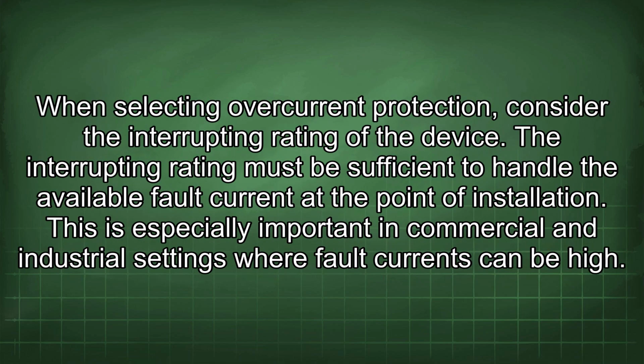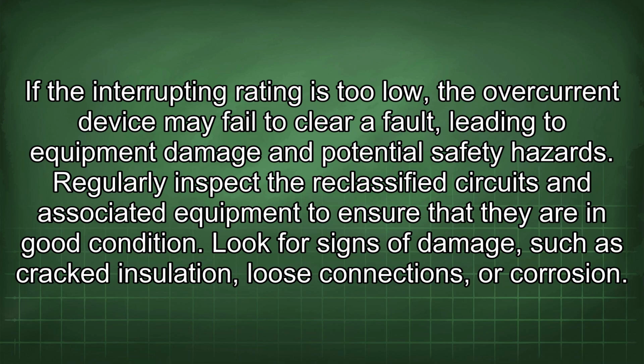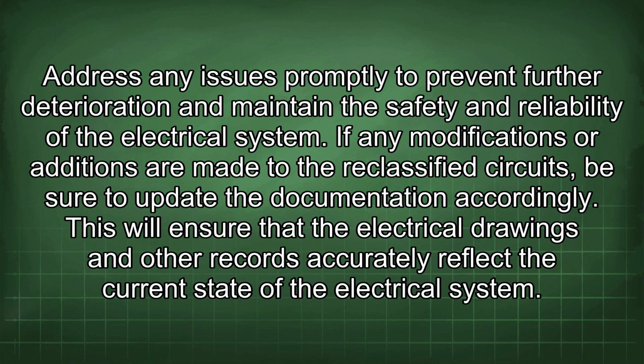When selecting overcurrent protection, consider the interrupting rating of the device. The interrupting rating must be sufficient to handle the available fault current at the point of installation. This is especially important in commercial and industrial settings where fault currents can be high. If the interrupting rating is too low, the overcurrent device may fail to clear a fault, leading to equipment damage and potential safety hazards. Regularly inspect the reclassified circuits and associated equipment to ensure that they are in good condition. Look for signs of damage, such as cracked insulation, loose connections, or corrosion. Address any issues promptly to prevent further deterioration and maintain the safety and reliability of the electrical system. If any modifications or additions are made to the reclassified circuits, be sure to update the documentation accordingly.